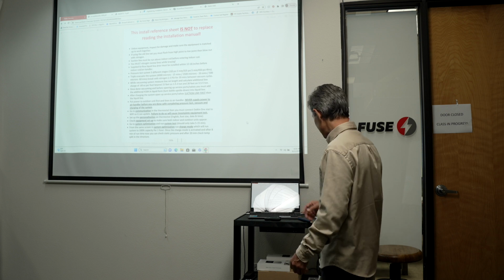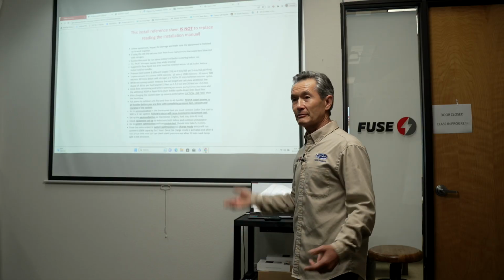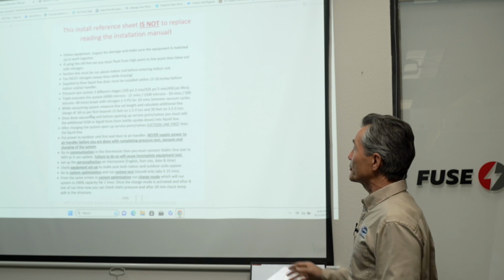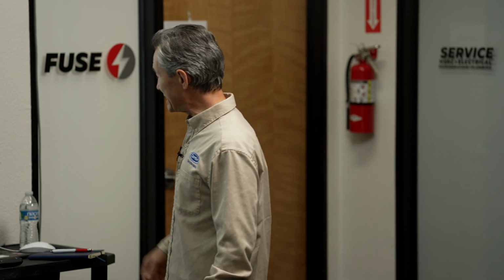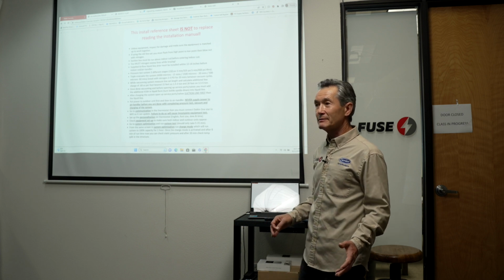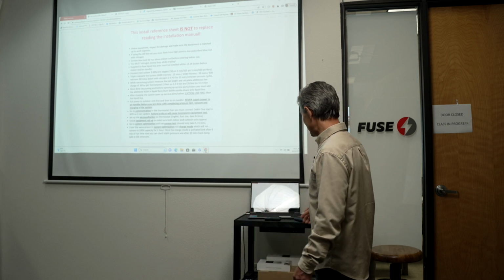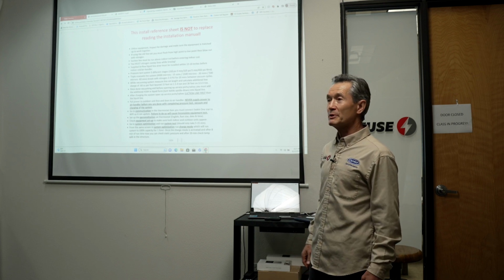So this note or guideline was provided by Daikin initially, from the beginning, before we start the installation. So you guys know, and probably many of you guys have seen it. So let's go through it. This is very important. Number one, when you receive the equipment, you have to inspect it. You guys already know, there were a lot of communications back and forth and discussions about it. Daikin maybe is not perfect at this point, so that's why there are certain defects or anything like that on the equipment. Before the installation, you have to inspect it. If it's minor and can be fixed on the spot, you guys can do it. If not, the equipment needs to be replaced.